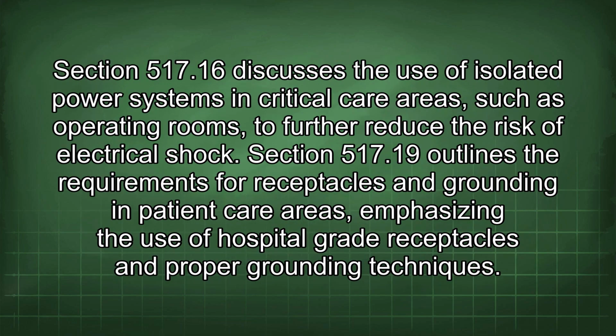Section 517.16 discusses the use of isolated power systems in critical care areas, such as operating rooms, to further reduce the risk of electrical shock. Section 517.19 outlines the requirements for receptacles and grounding in patient care areas, emphasizing the use of hospital-grade receptacles and proper grounding techniques.